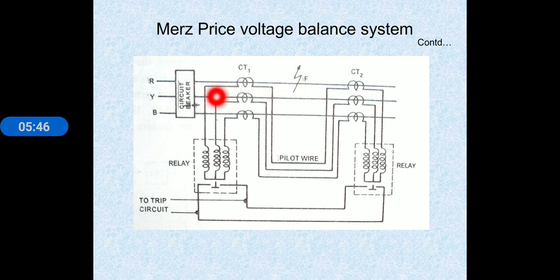Each phase has one current transformer mounted like that. Three current transformers are mounted, one on each phase. Here the representation has been done like that, CT1 and CT2. Each current transformer's secondaries are connected in series by using pilot wires, and the other end is connected through the relay. Here also, current transformer 2's secondary end is connected through the relay.